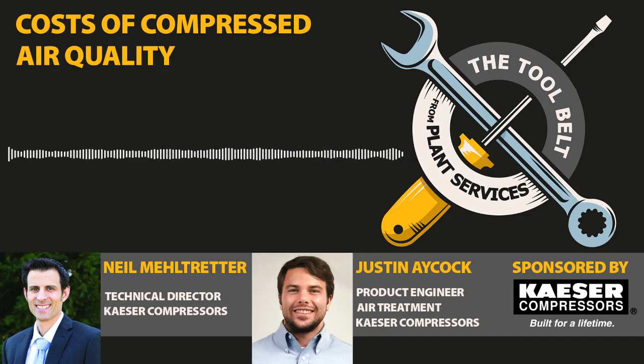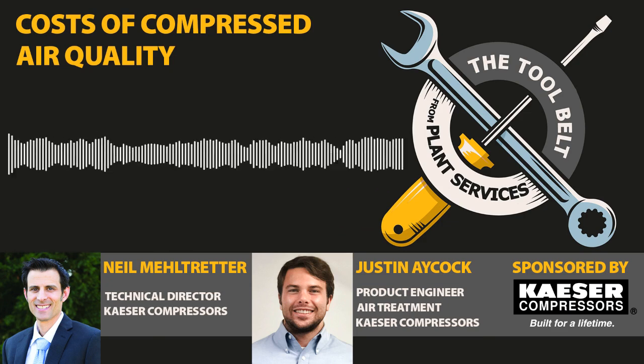Yeah, Tom. So, compressed air dryers are sized based on pressure and temperature, and the filtration is usually sized based only on pressure. So, if your pressure goes up, the capacity of your air treatment goes up. So, when plants say they need more pressure and they ramp up their compressor, this leads to the air treatment having more capacity. So, yep, you're going to have an insurance that your air treatment is going to work well because you're increasing the capacity of the equipment.